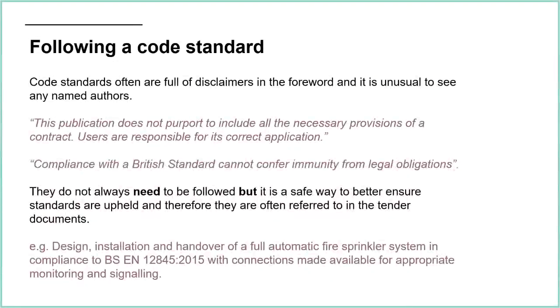In some circumstances, you would need to follow a code standard. For example, in the building codes, Approved Document B in the UK, where the limit for residential buildings is now 11 metres. It specifically says that it should be a sprinkler system conforming to BS 9251 within that.